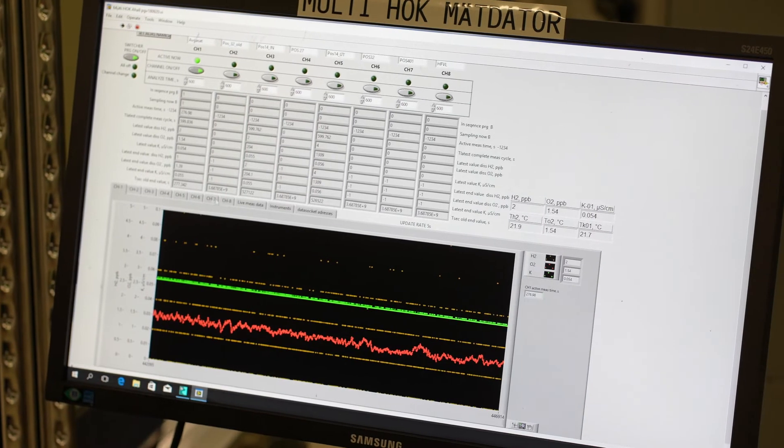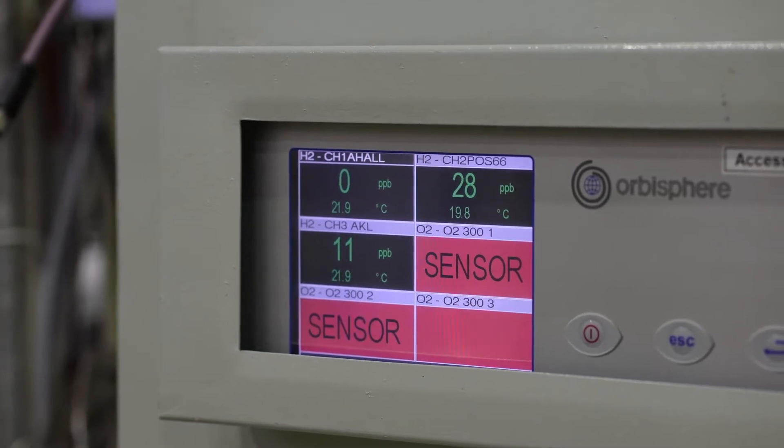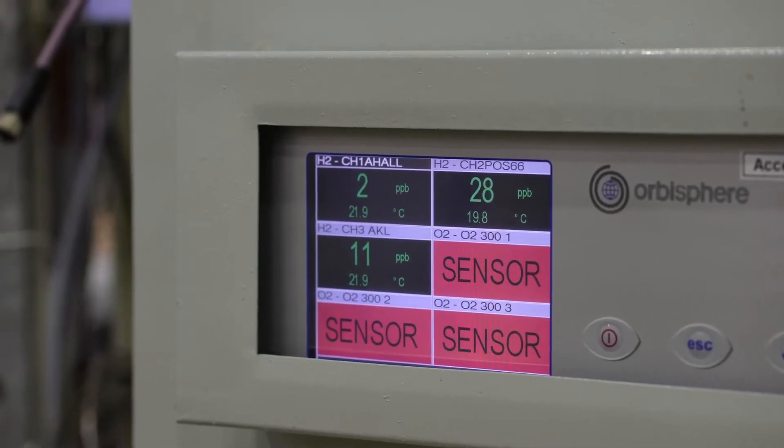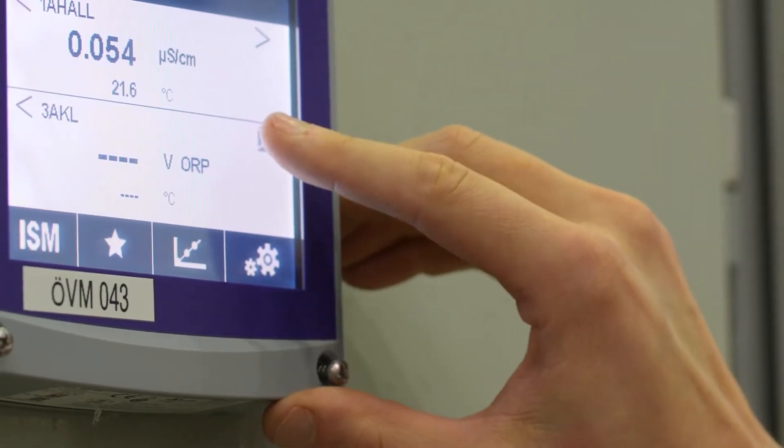The laboratory is equipped with an in-house developed PC-controlled, multi-channel valve regulated water chemistry monitoring system. The system measures conductivity, dissolved hydrogen, and oxygen in water from the various test positions in the laboratory.